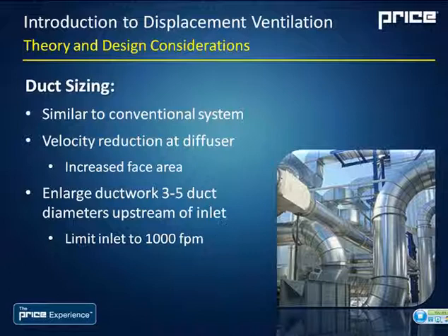The one recommendation we do make is that you enlarge ductwork about 3 to 5 duct diameters upstream of the inlet. So if you're doing a transition into the room, let's say for a corner or a wall diffuser, you want to do that maybe above the ceiling and give it 4 or 5 feet of enlarged ductwork to limit your inlet velocities to around 1,000 feet per minute, and that's just for noise concerns.